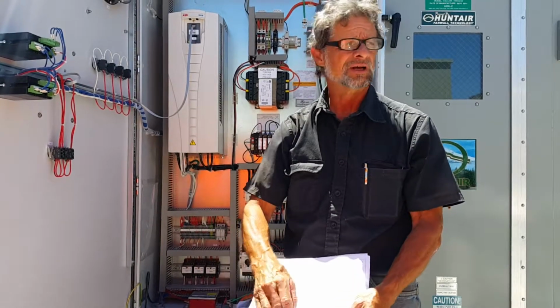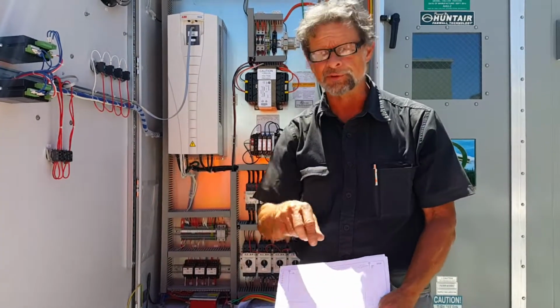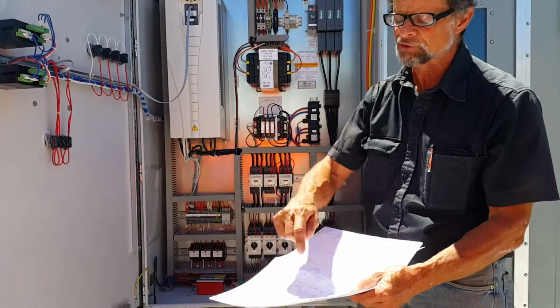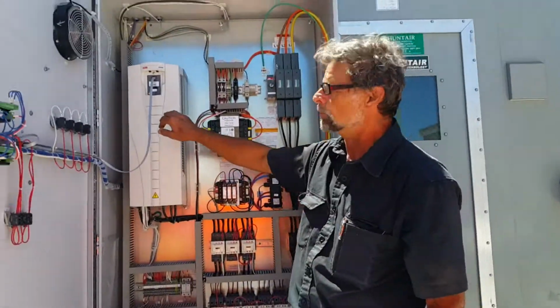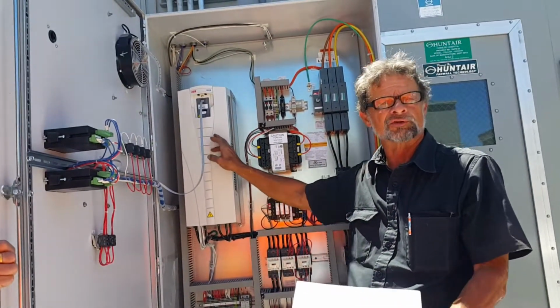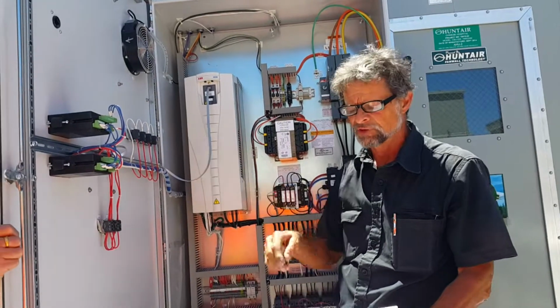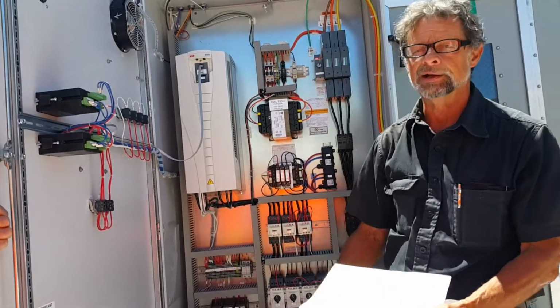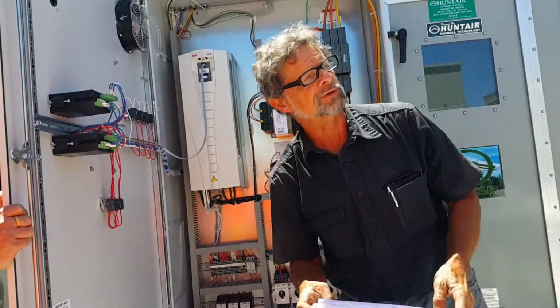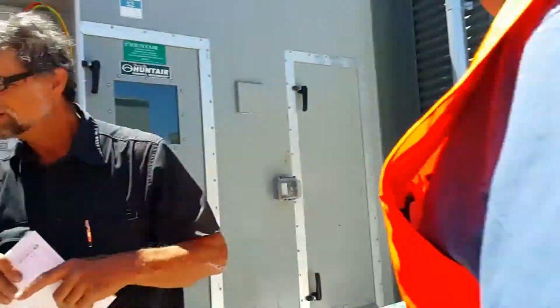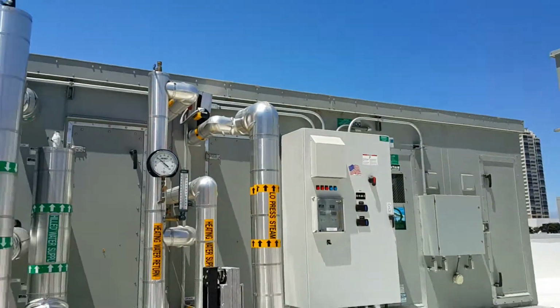So there's a contact that comes from each drive. And if one drive blows up, goes into alarm or something, it switches in alarm contacts, and it'll automatically switch to the other drive. Look at the lights. So you see that's got 2 blue lights.